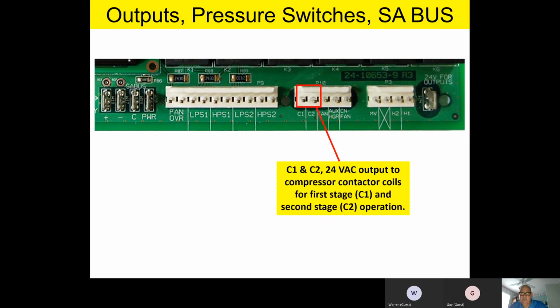Right next to that is C1 and C2. This is a 24-volt output for our compressor contactor coils. So again, our compressors are going to come on with a contactor. This is what controls the contactor coils for first and second stage compressor operation.